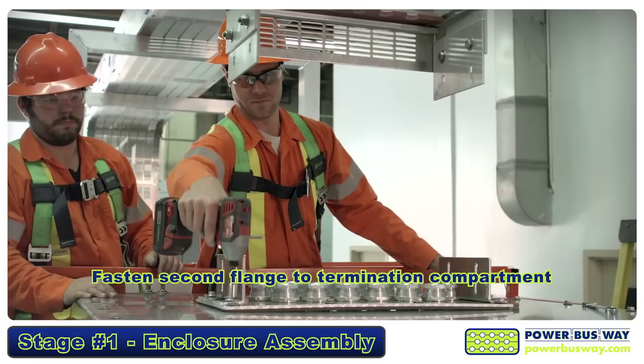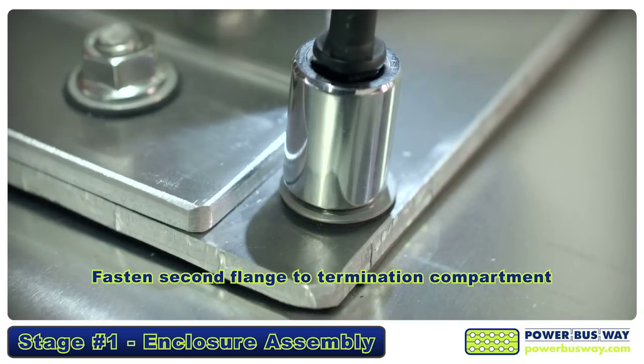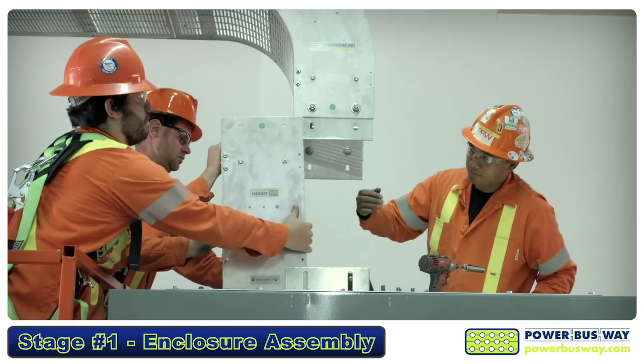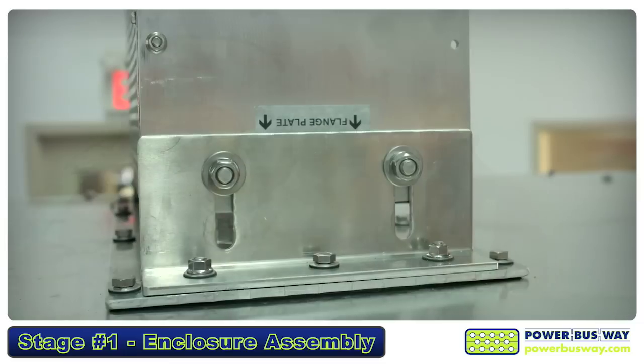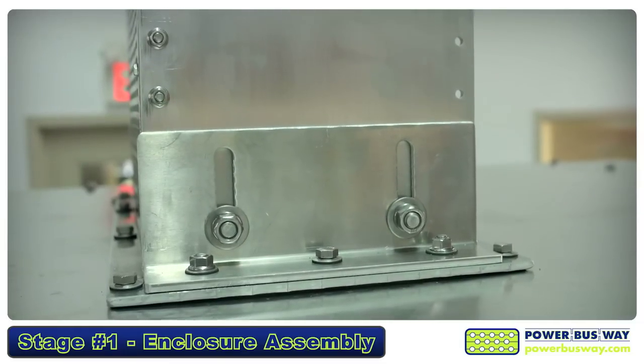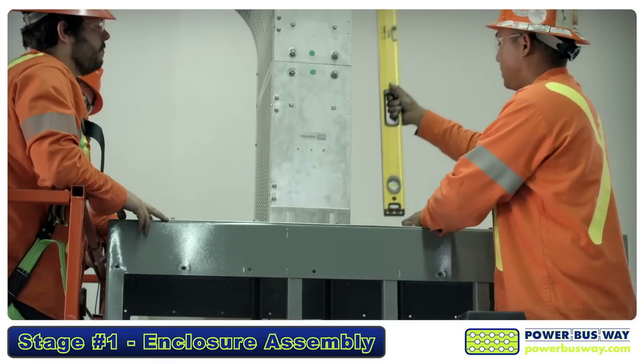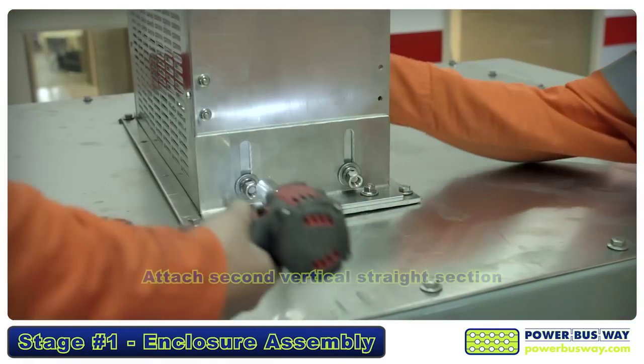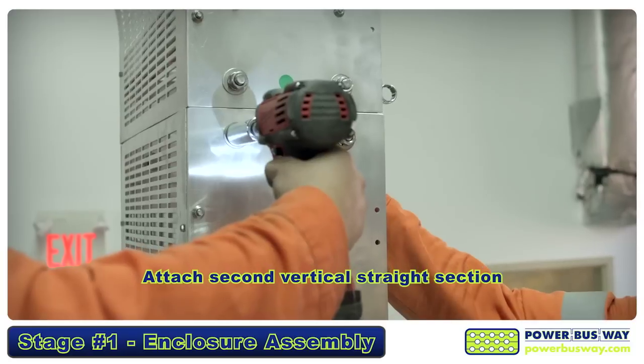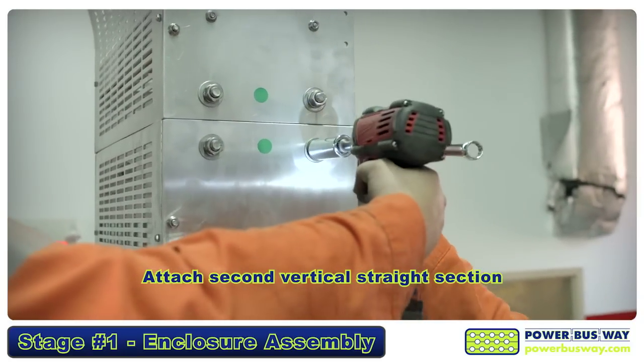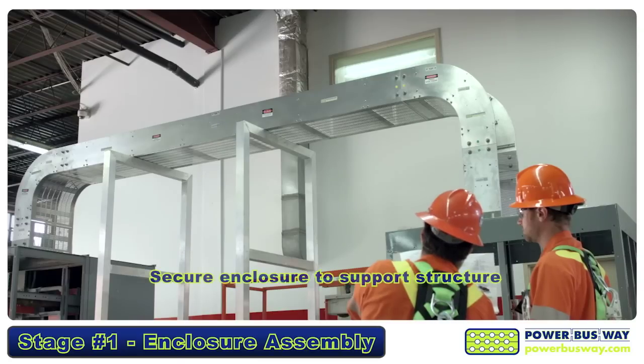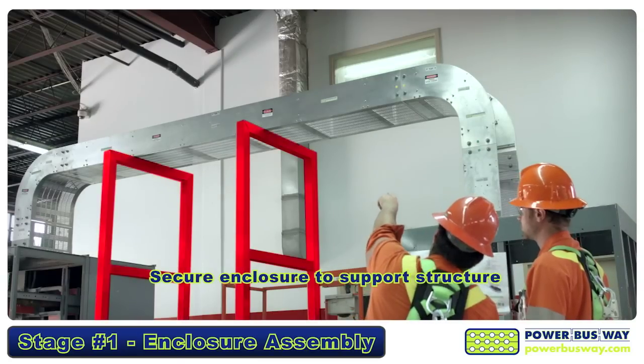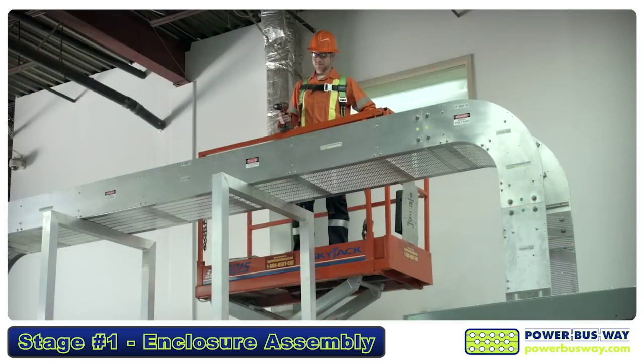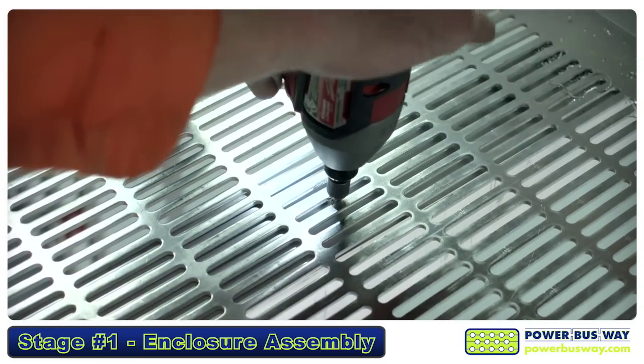Once the equipment entry window has been cut, fasten the second flange to the termination compartment. Align the vertical straight section and adjust accordingly if necessary. Verify that the enclosure is level before tightly attaching the vertical straight section to both the flange and the vertical 90-degree fitting. Finally, secure the cable bus enclosure to the support structure. Once the entire enclosure is in place, proceed to Stage 2, Cable Installation.